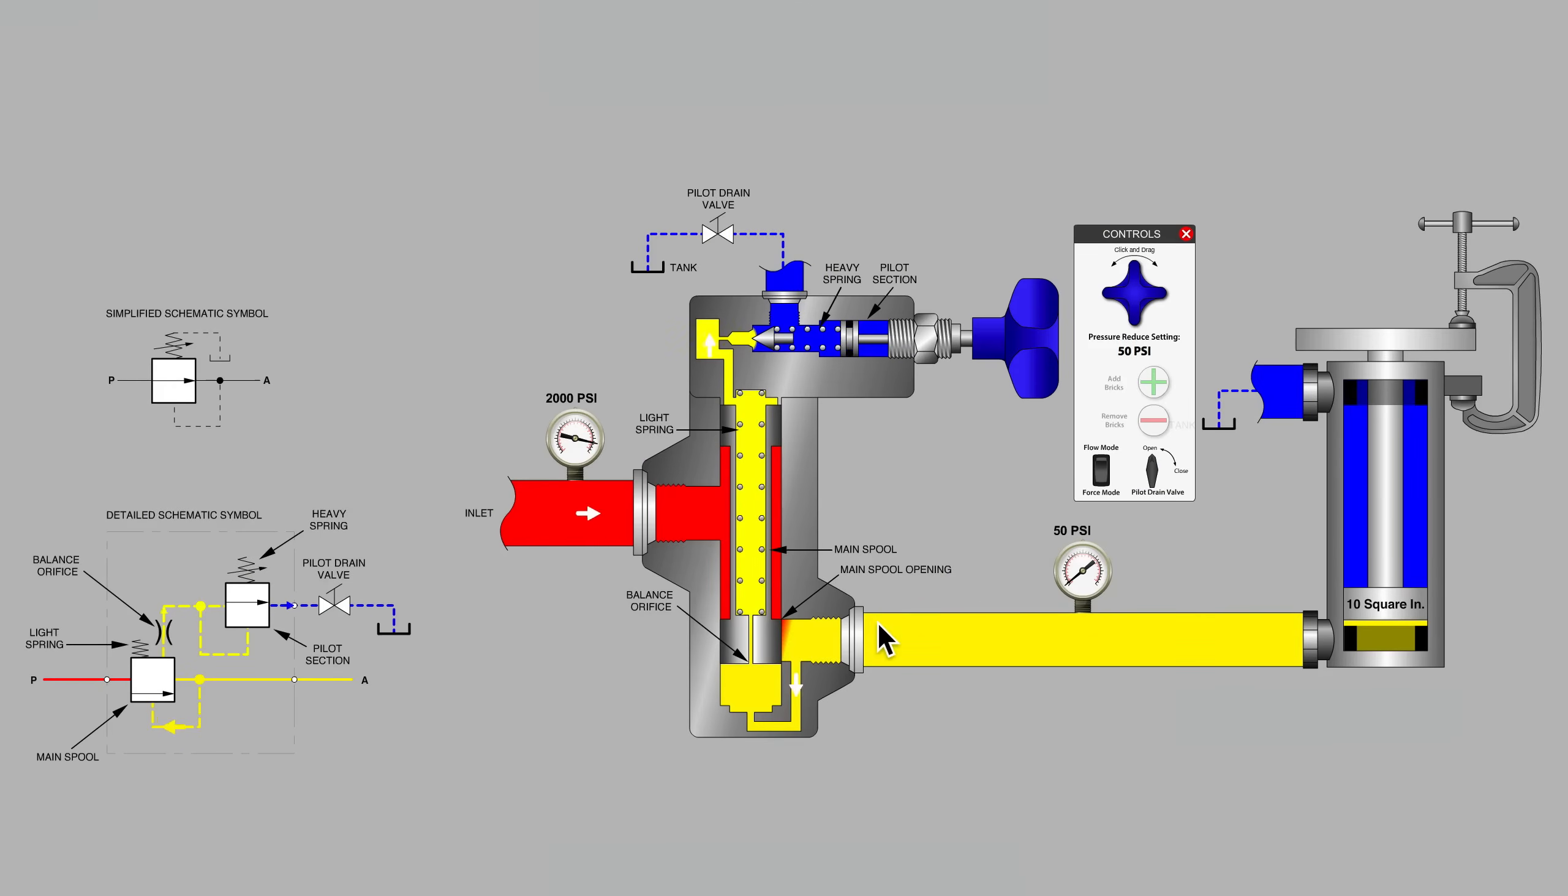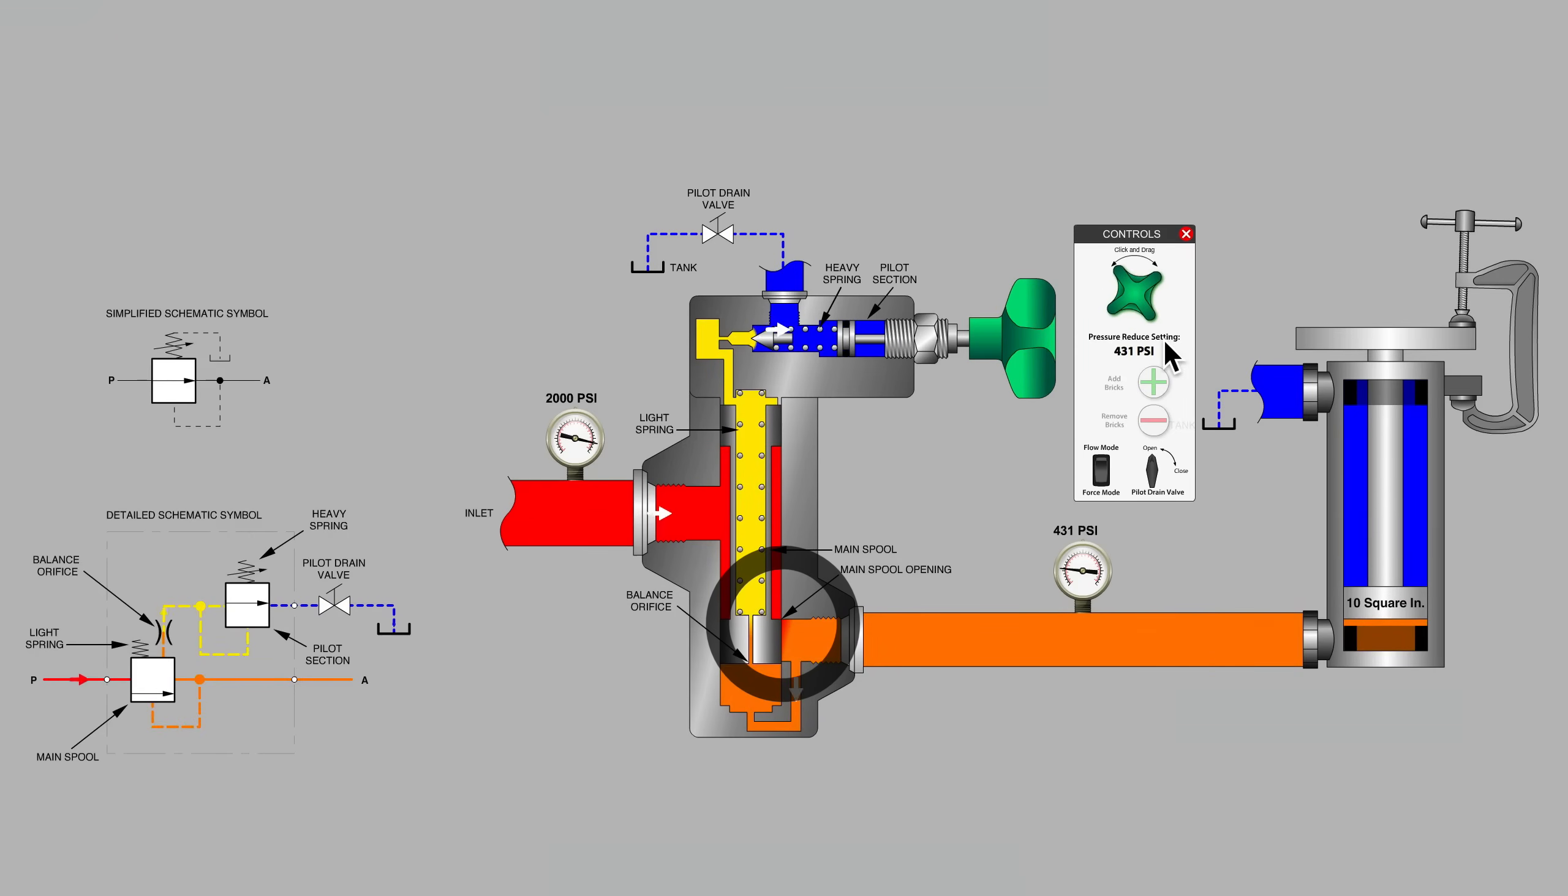Remember that there is no continuous flow path in this sub-circuit to the cylinder. Observe here at the main spool opening. If we quickly increase the pressure setting of the valve, the spool is opened for a longer period of time in order to bring more of the inlet pressure through to the outlet.